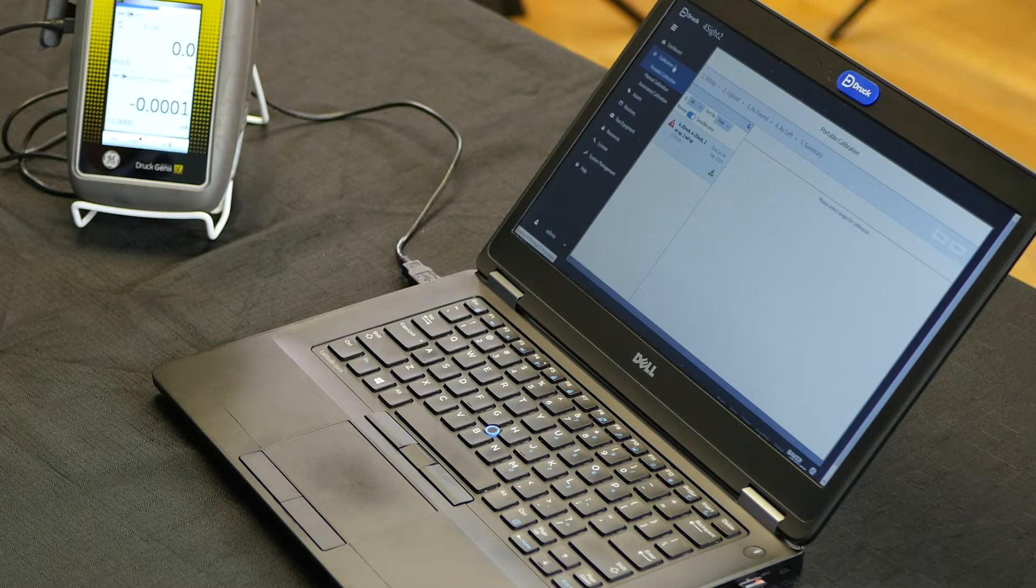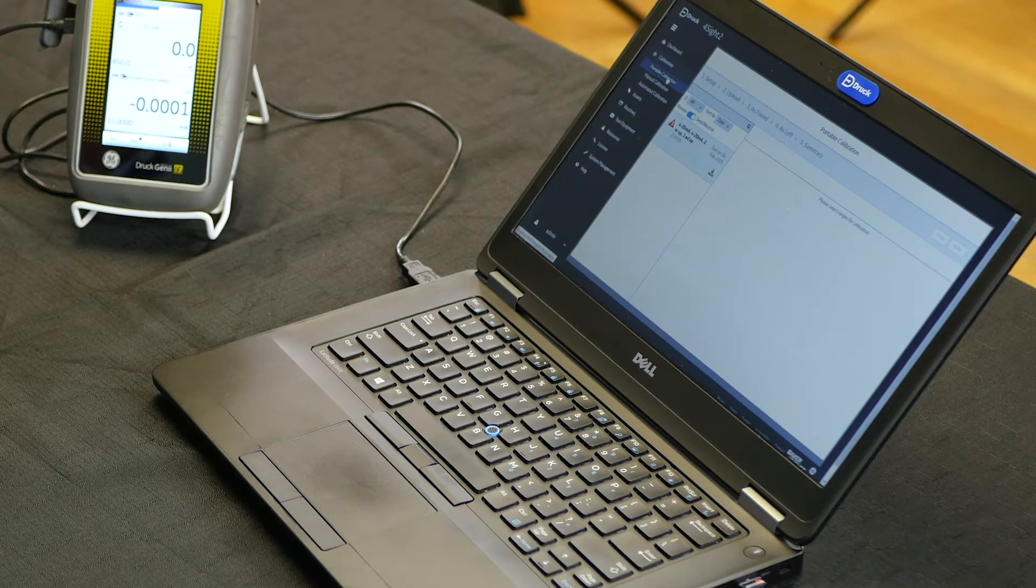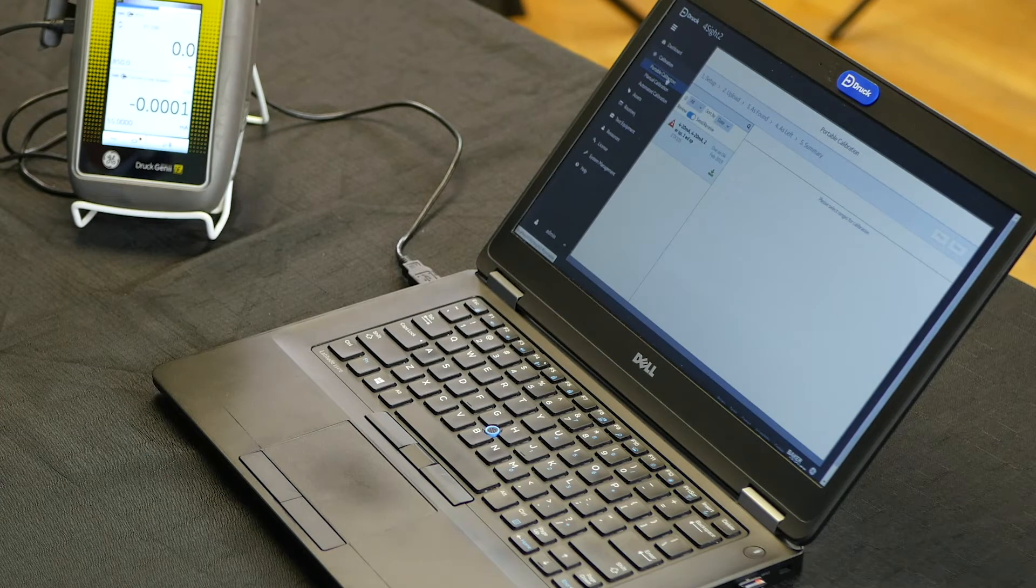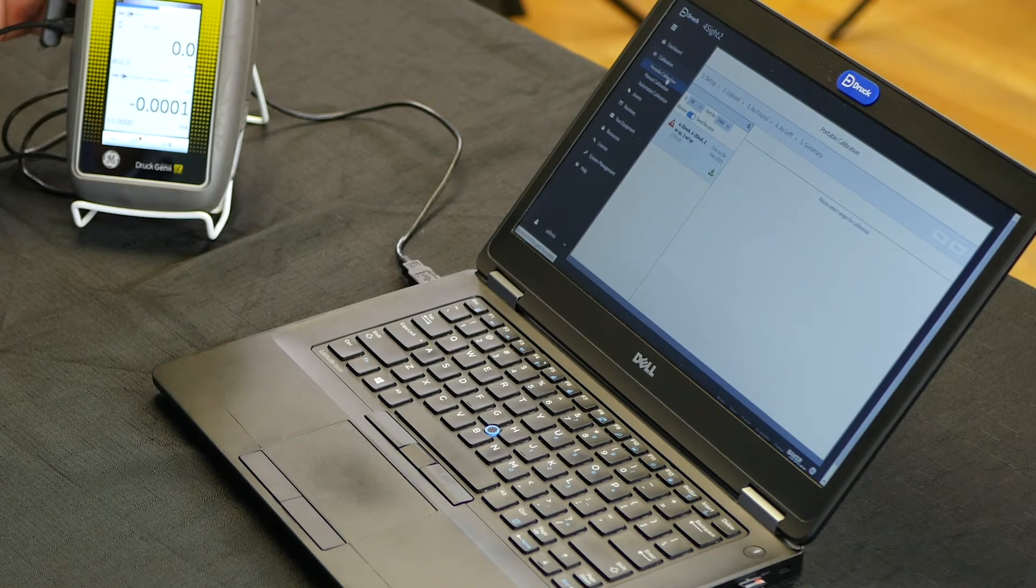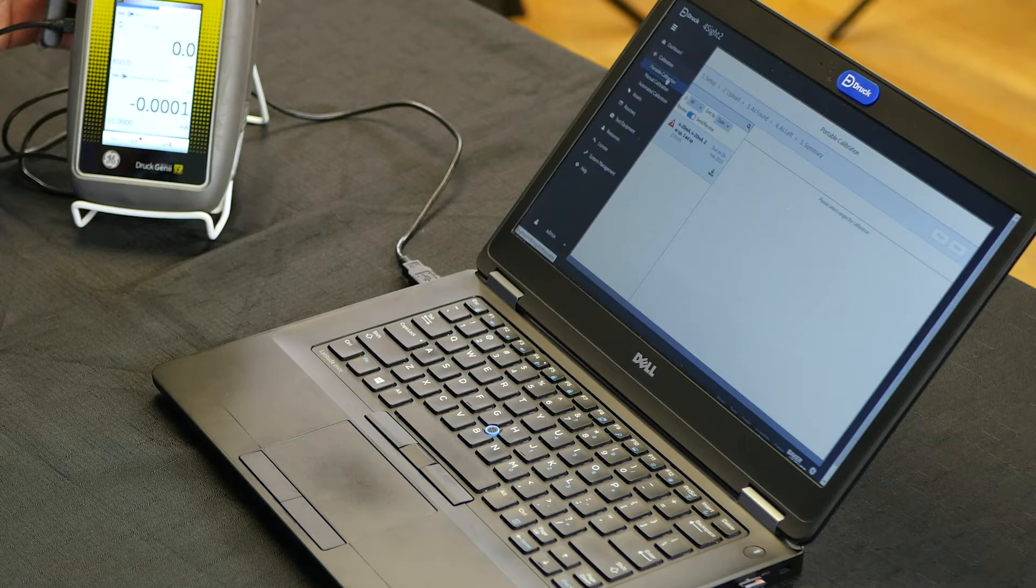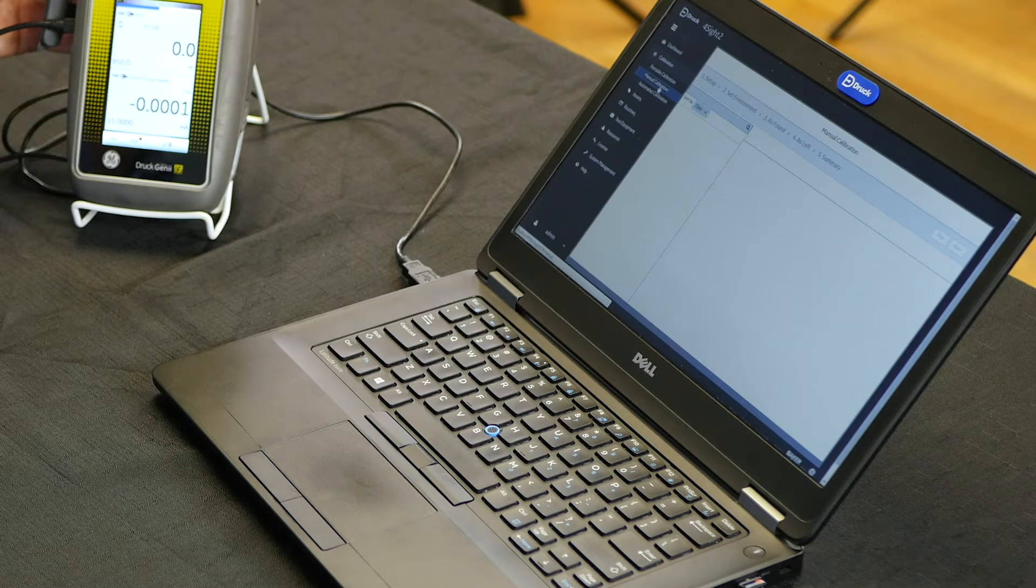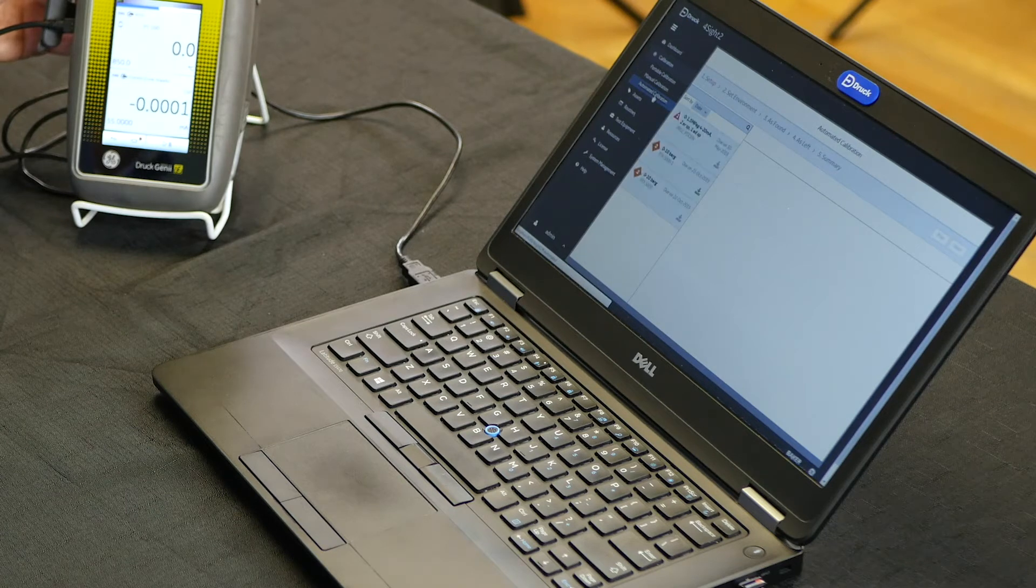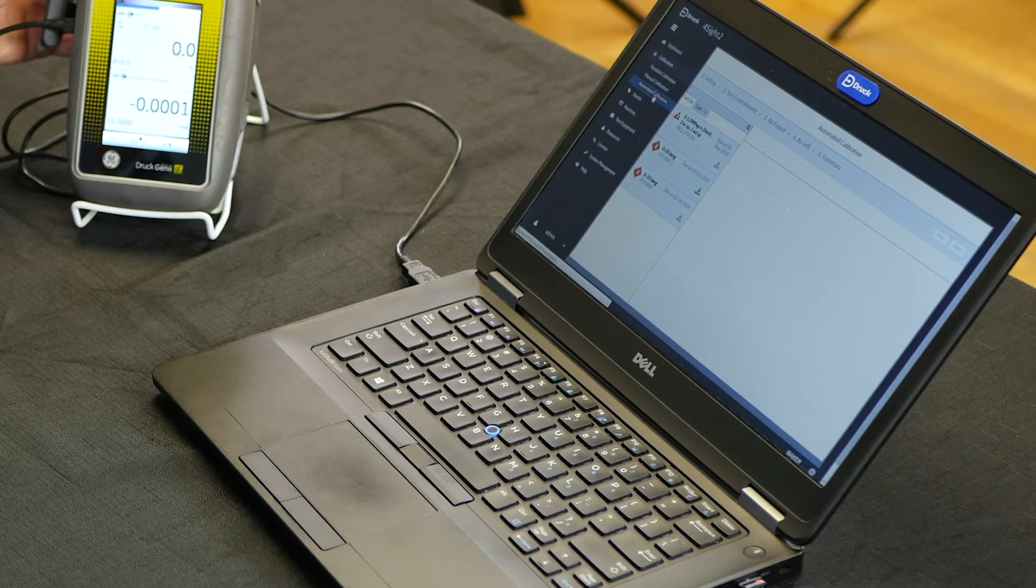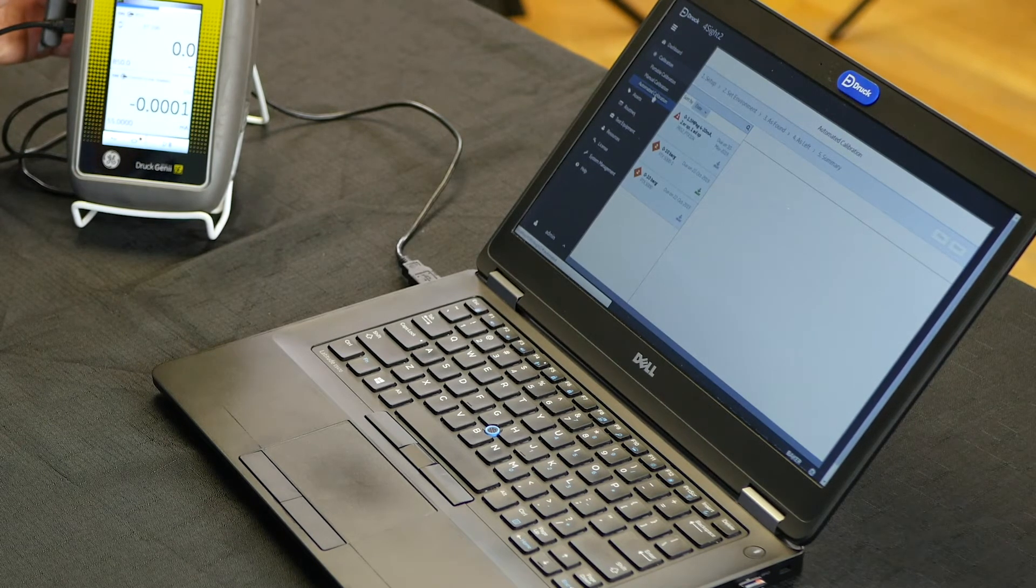Working down the menu, we can step into the calibration mode which facilitates performing portable calibration with interconnectivity to our DPI 600 series portable calibrators. Manual calibration allows you to perform calibrations on other devices if you don't have a connected device. Automated calibrations are available if you have a PACE pressure controller, enabling fully automated pressure calibration.